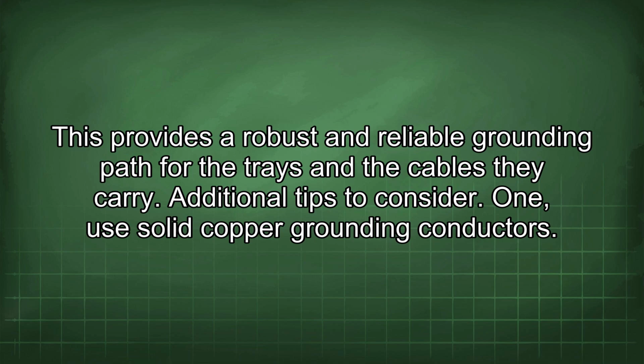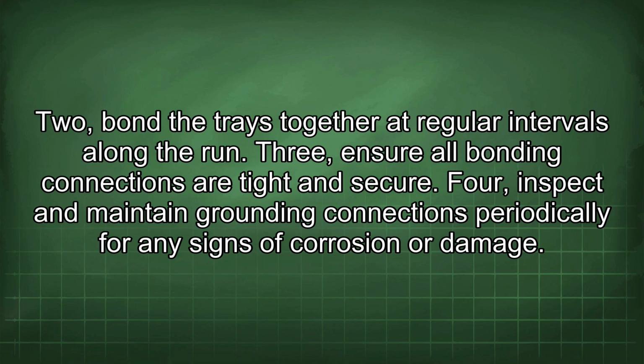Additional tips to consider: 1. Use solid copper grounding conductors. 2. Bond the trays together at regular intervals along the run. 3. Ensure all bonding connections are tight and secure. 4. Inspect and maintain grounding connections periodically for any signs of corrosion or damage.